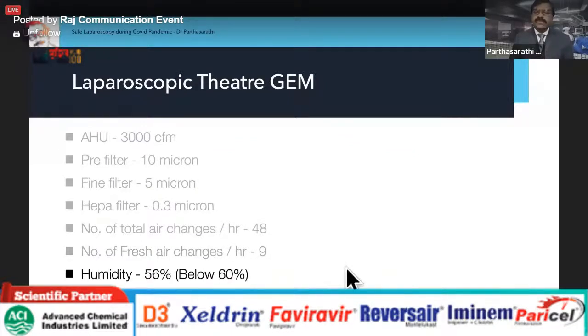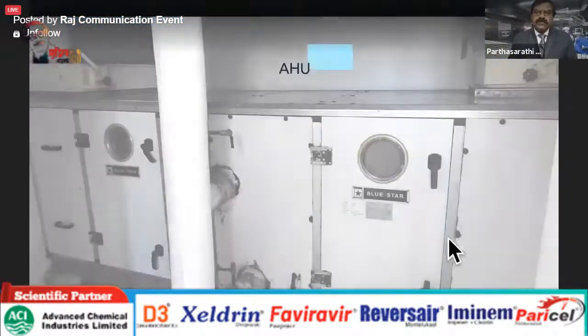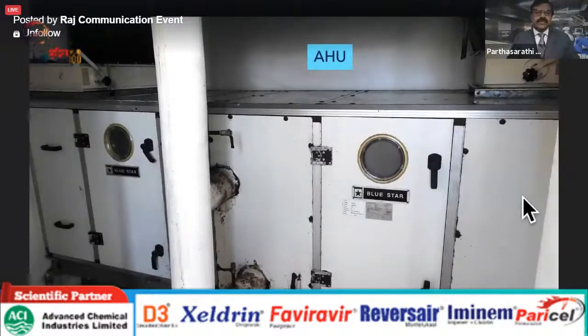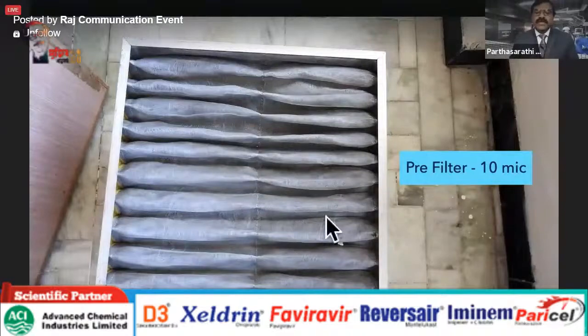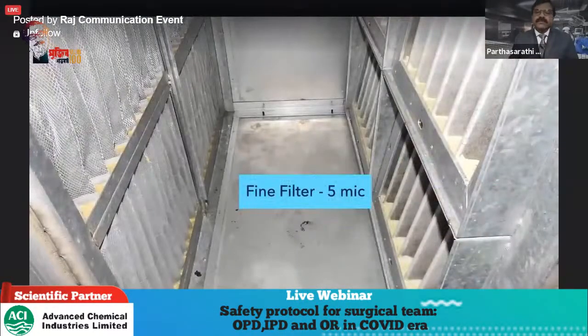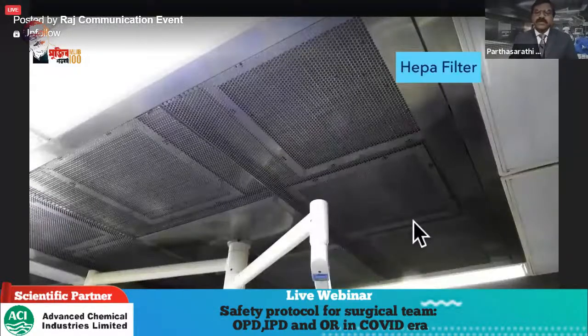Within the 48 cycles, the fresh air changes will be 9. Humidity should be 30 to 60, below 60. And fresh air in the OT is 20% of the total air. So these are all the criteria we are following. The recommendation is 6 fresh air changes per hour, but ours is 9, and 40 total air changes, ours is 48. This is our AHU, you can see what a big one it is, 3,000 cubic feet, so the number of air cycles is more. This is the pre-filter, which does 10 micron filtering, these are the other 5 micron filters, and within the OT this is the HEPA filter, with 0.3 micron filtering capacity.